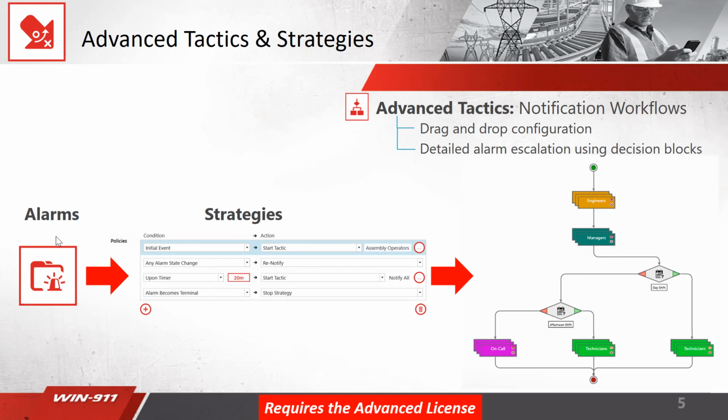Let's take a look at your advanced tactics and strategies. Still, the same process is in place. Your alarm triggers a strategy, which triggers a tactic. Your strategy is the policy of actions to put in place. In this example, the initial event happens and it starts a tactic called assembly operators. If any alarm state changes, we will re-notify all those users. You can turn this feature on and off.